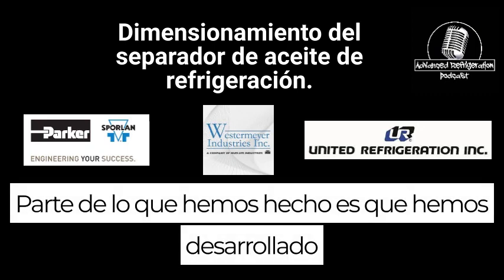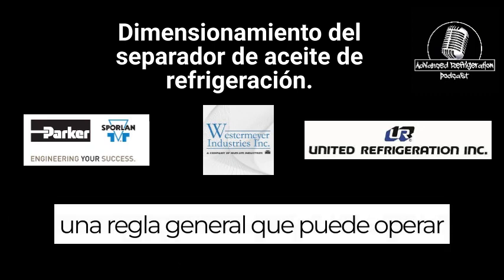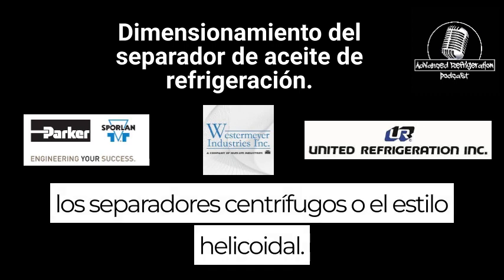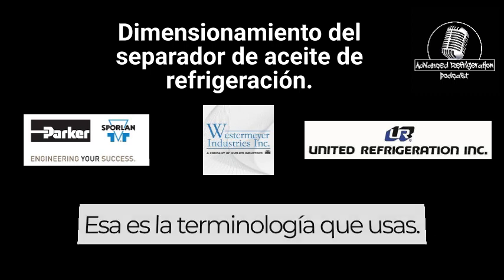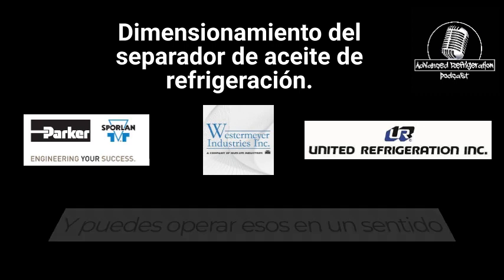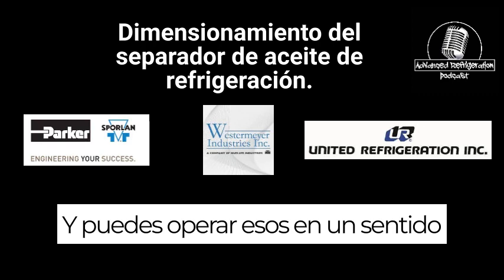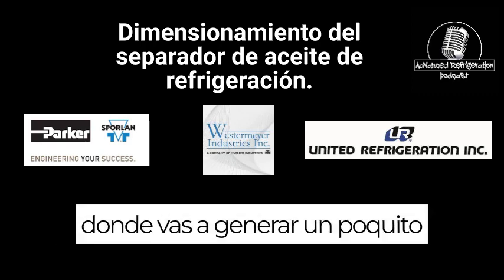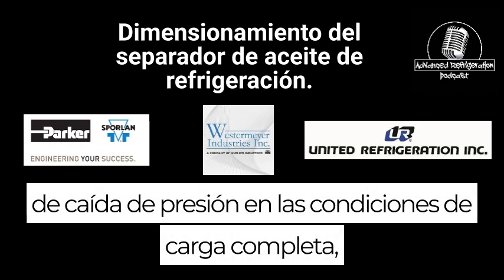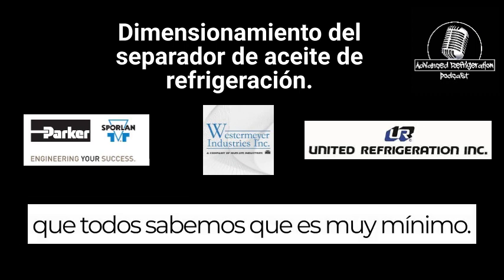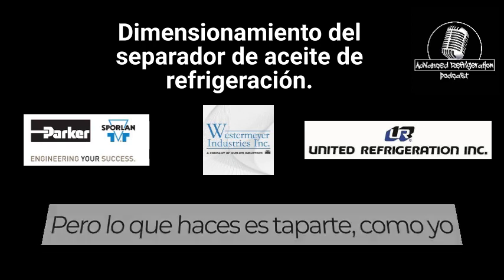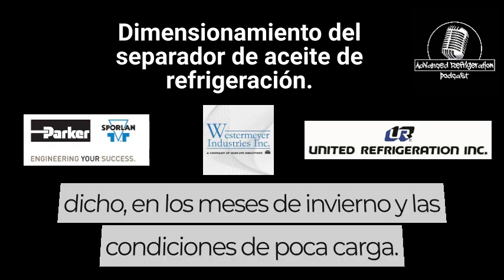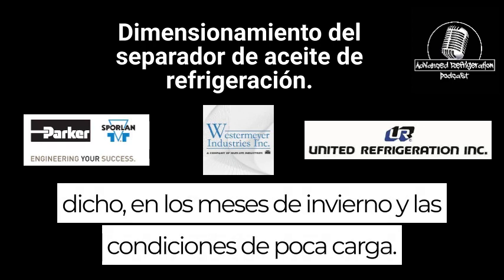Part of what we've done is develop a rule of thumb that you can operate the centrifugal separators, or the helical style, that's the terminology that you use. You can operate those in a sense where you're going to generate a little bit of pressure drop on the fully loaded conditions, which, we all know, is very minimal. But what you do is cover yourself, like I said, on the winter months and the low load conditions.